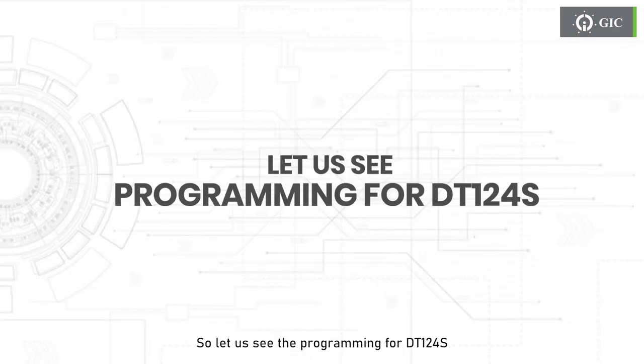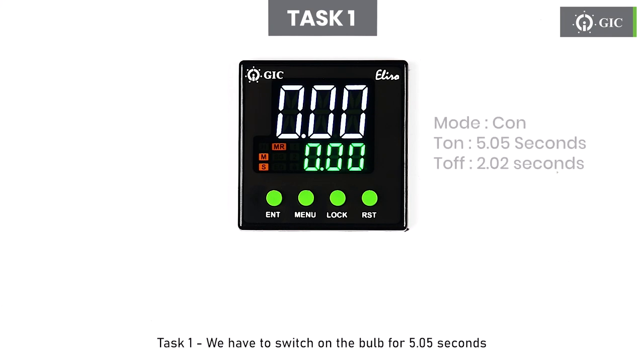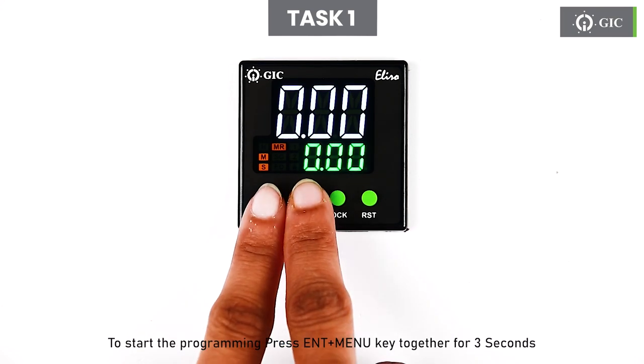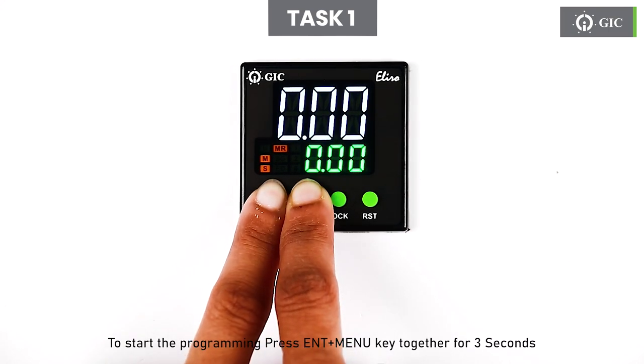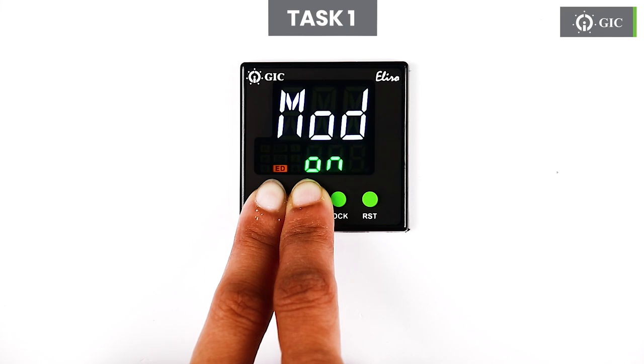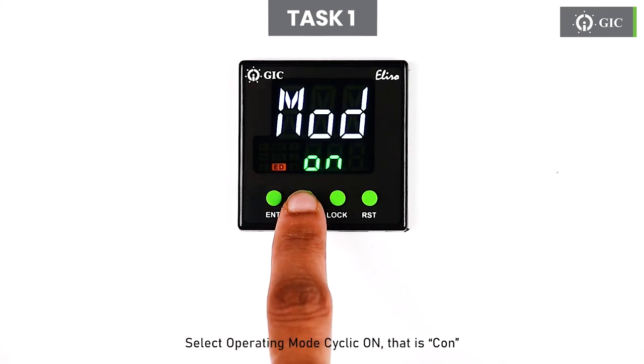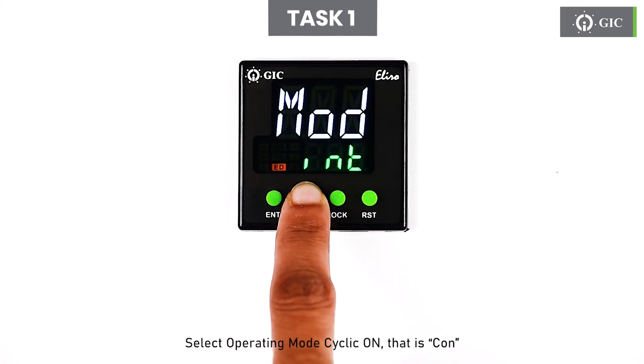So let us see the programming for DT124S. Task 1. We have to switch on the bulb for 5.05 seconds, then switch off for 2.02 seconds, and again switch on. To start the programming, press Enter and Menu key together for 3 seconds. Select operating mode, cyclic on, that is CON. Press Enter to save the selection.